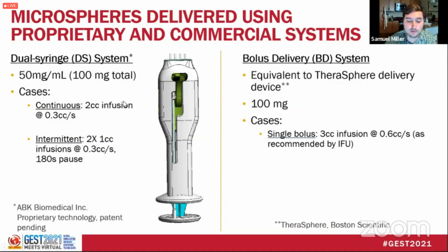For this device, 2 cases were evaluated: a continuous administration of a 2 cc infusion, and intermittent administration of 2 1 cc infusions with a 3-minute pause in between. For the bolus delivery system, a single 3 cc bolus case was tested in accordance with the manufacturer's specifications.